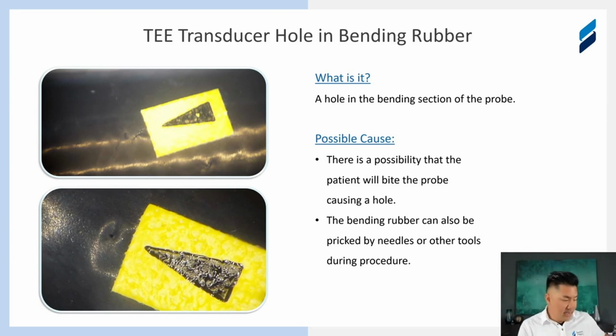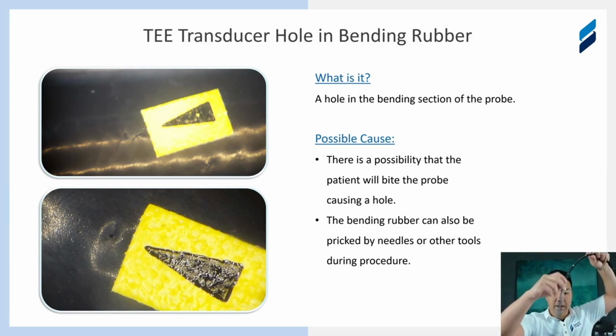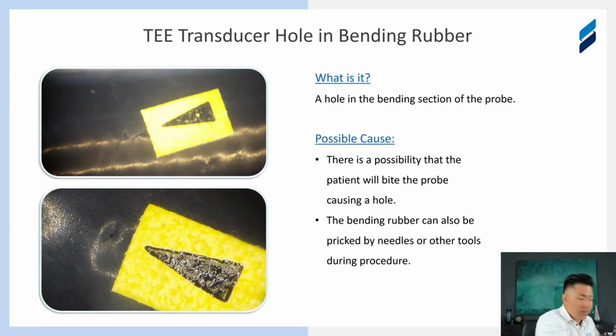The danger here is that if it's not caught early, well, TEE probes are stored upside down like this, straight, so the insertion tube doesn't curl and assume a curled position. So if you look at how gravity works, all the fluid entering from a micropuncture in the bending rubber will now fall right to the crystal. So I highly recommend that you catch it early, get it repaired early, and you can avoid a really costly replacement on these TEE probes.